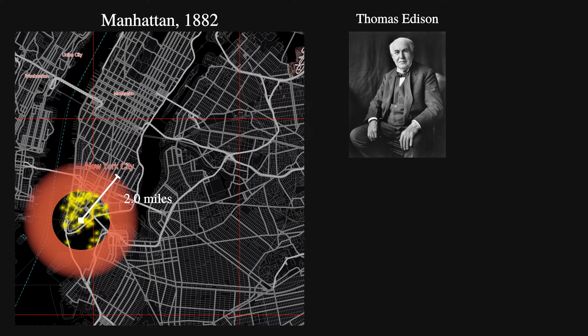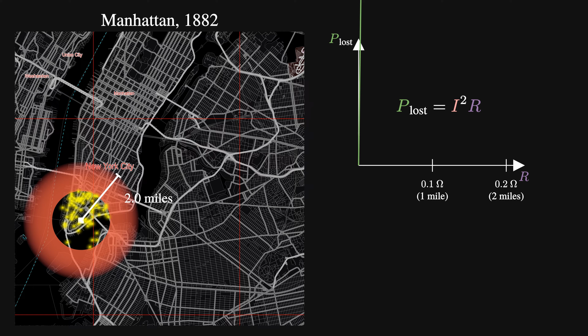The reason for this is this very simple equation, which states that the power dissipated by a wire when a current passes through it is the current squared times the resistance. This power loss, which we'll plot as a function of R, was so huge that the wires would glow red hot. But this might seem quite strange, as these wires are made of copper, which is a very good conductor. Even 2 miles worth of copper cable only has a resistance of about 0.2 ohms. So the resistance clearly isn't the problem here, it's the current. But why was this current so huge?